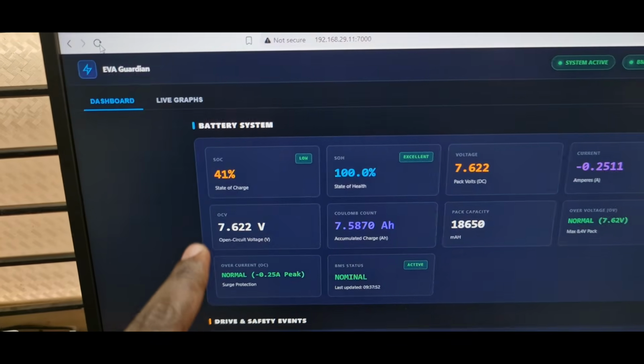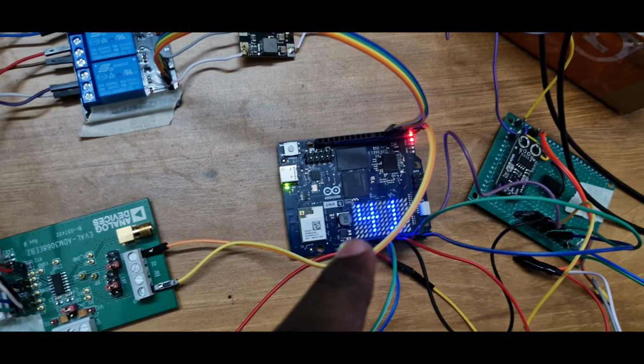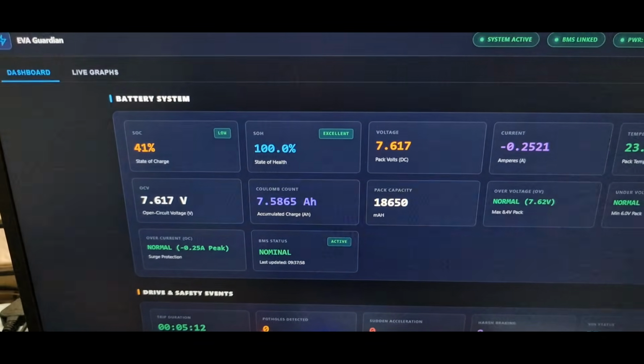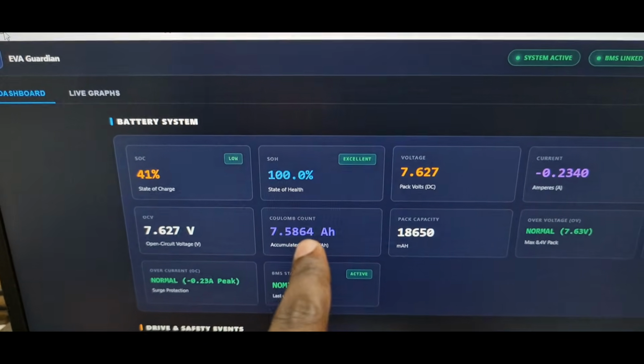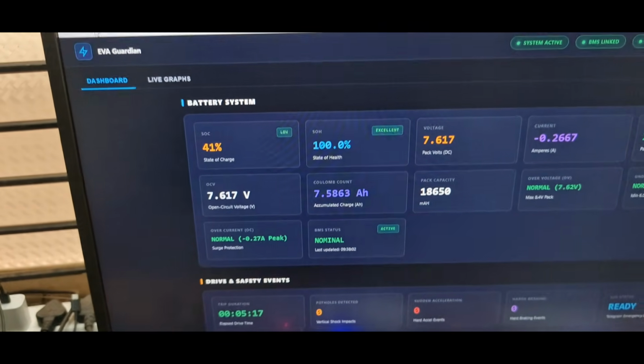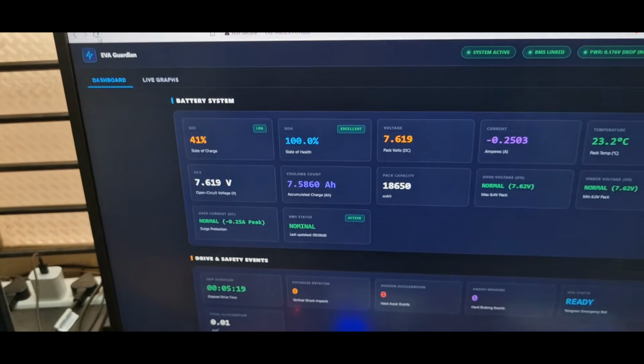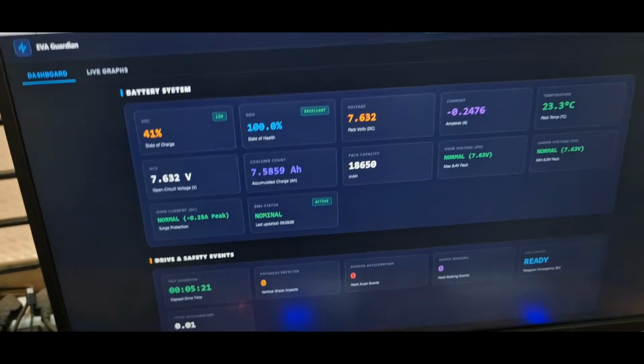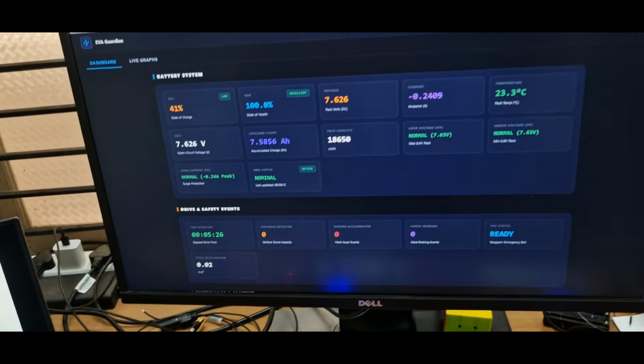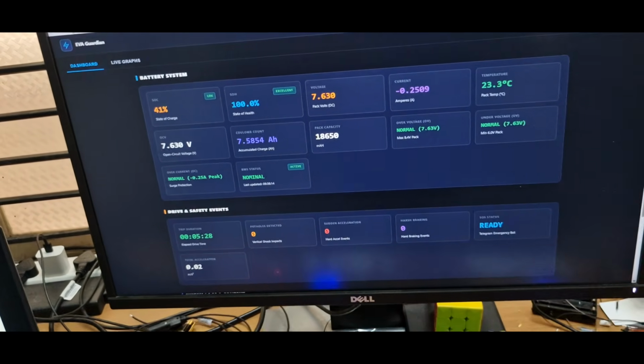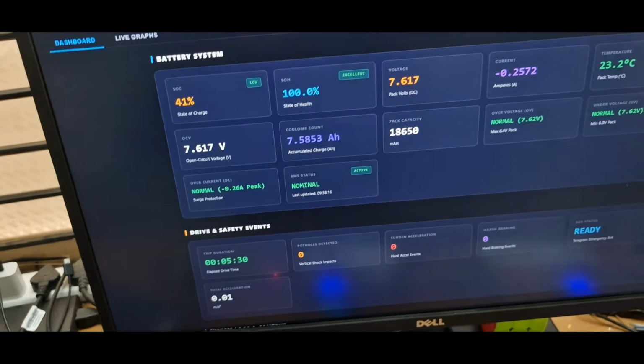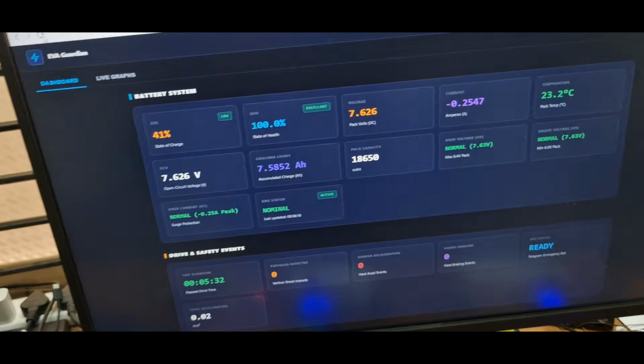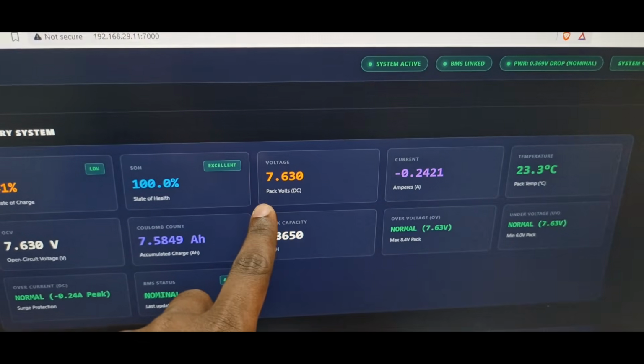Here you can see the SoC, state of charge, as 41%, and here also in the display it is showing 41%, and SoH it is showing as 100%. Actually, to do an SoH, we need to collect a huge amount of data of charging and discharging cycles. But as of now, for this project, the algorithm is implemented to calculate an SoH. It will always show 100% because there is not much charging and discharging cycle of the battery happening in this section. And the voltage I am measuring is 7.63 volts.